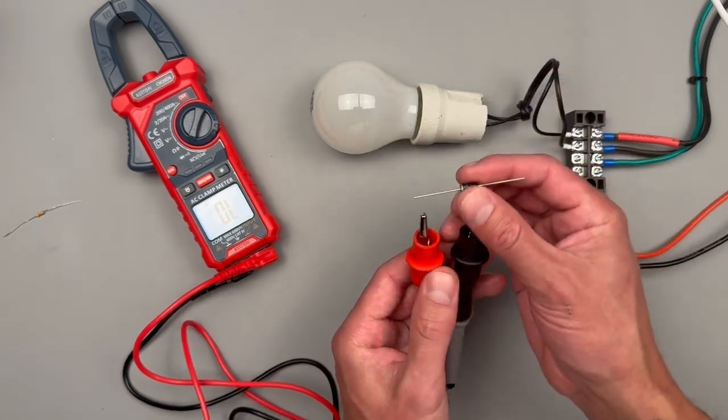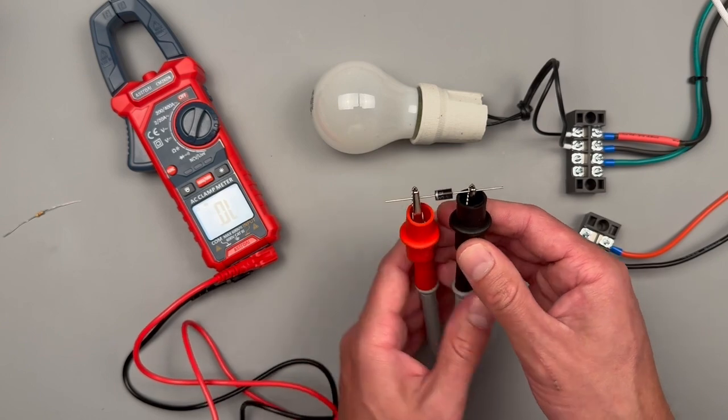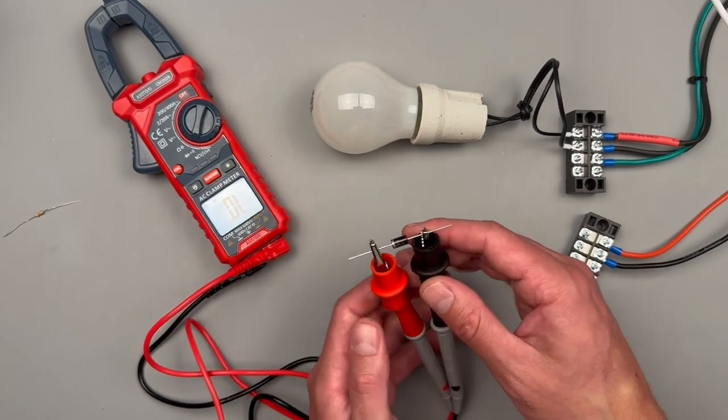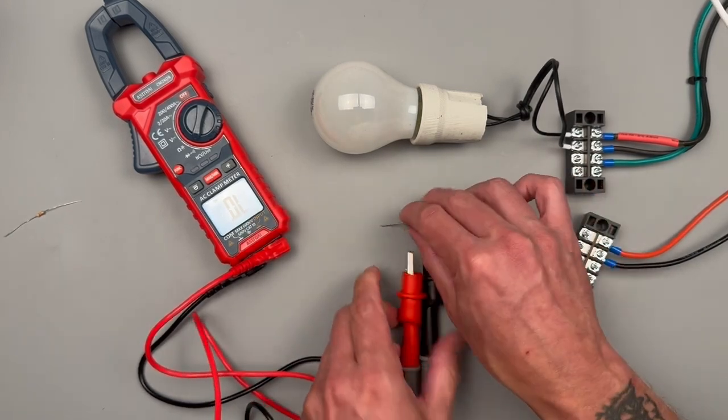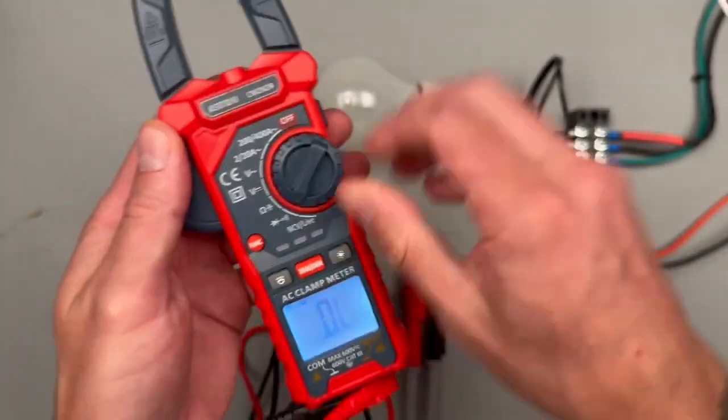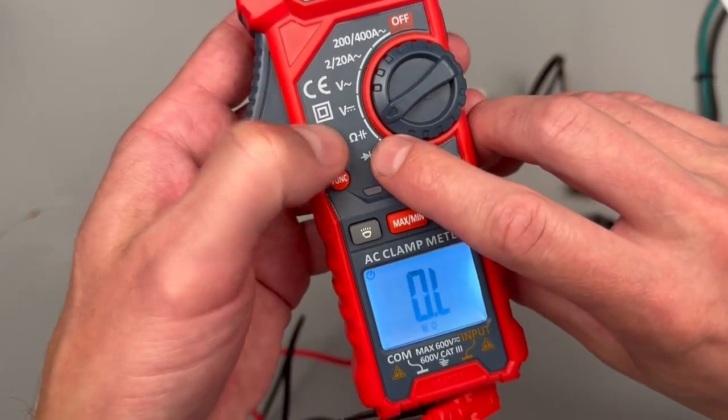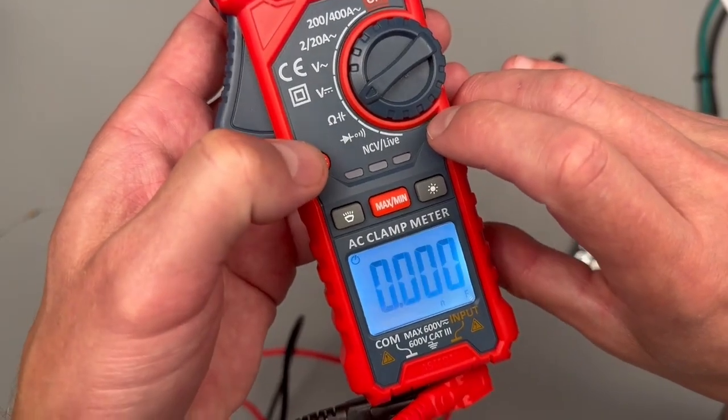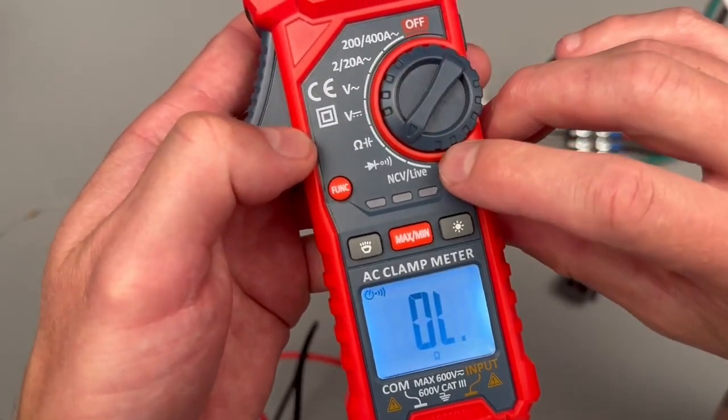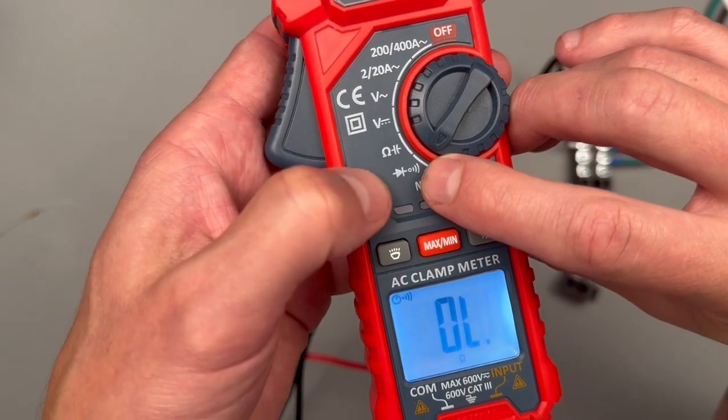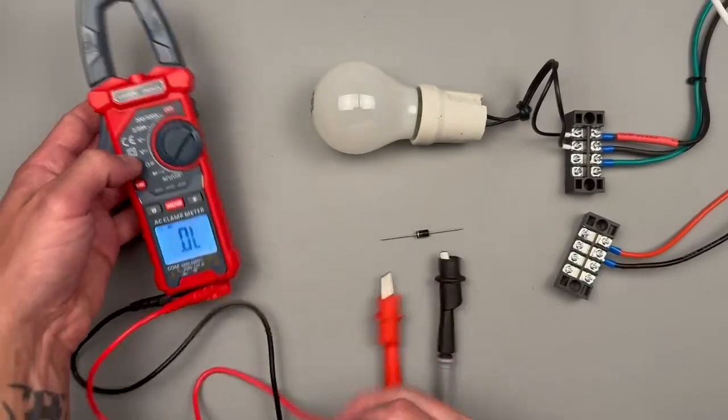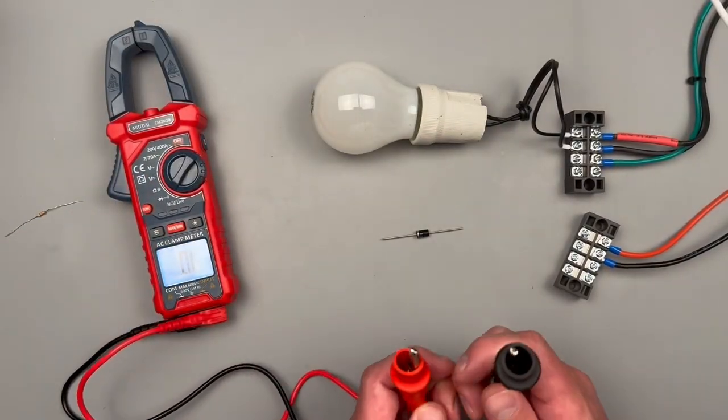And then we'll always test our diodes in both directions. So we'll flip it, we should have no flow, and you should have an OL on your meter. OL stands for a few things: could be open loop, could be over limit, just depends on the context of the testing that you're doing. And a way to verify that you're on the diode setting is that little arrow with that line, it's for your diode. The way that they have it set up, this one will default to continuity, and if you press function then it will go to diode testing. Pay attention to the screen and what the meter wants to default to and keep an eye on that.